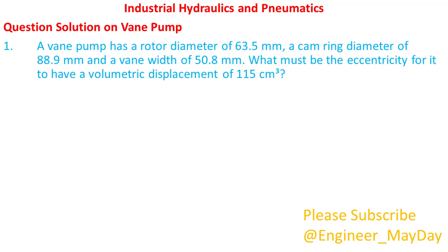Let's tackle this question. A vane pump has a rotor diameter of 63.5 millimeters, a cam ring diameter of 88.9 millimeters, and a vane width of 50.8 millimeters. What must be the eccentricity for it to have a volumetric displacement of 115 cubic centimeters?